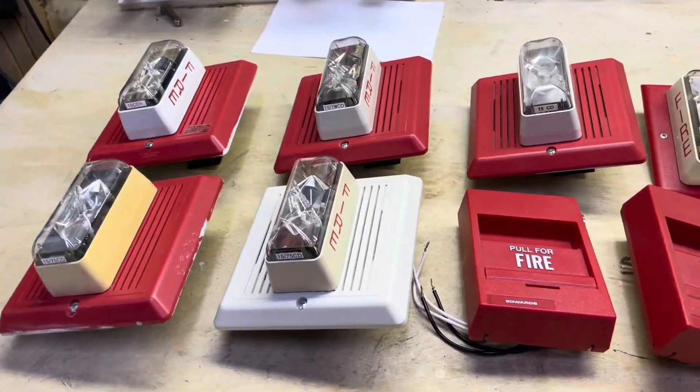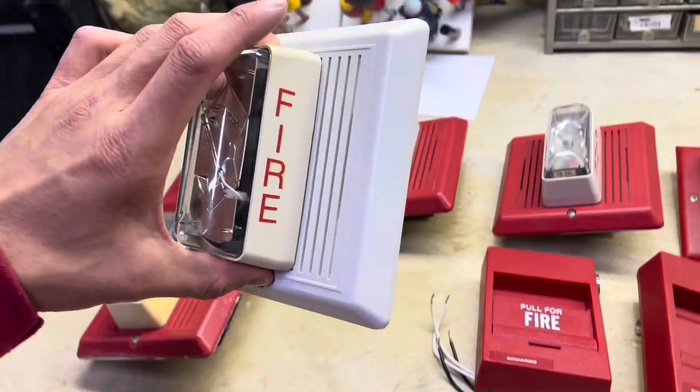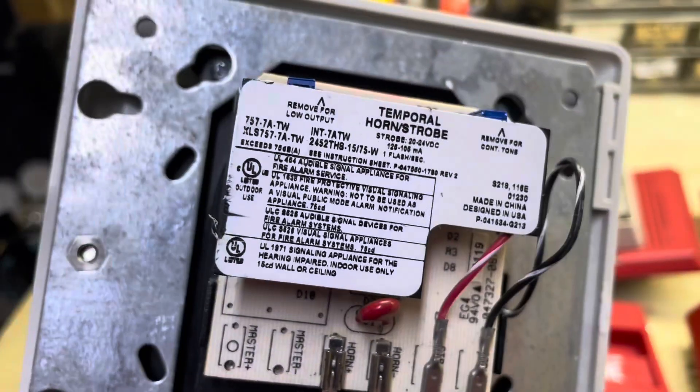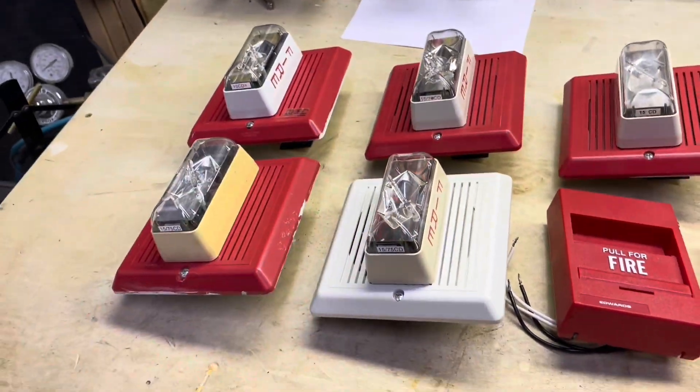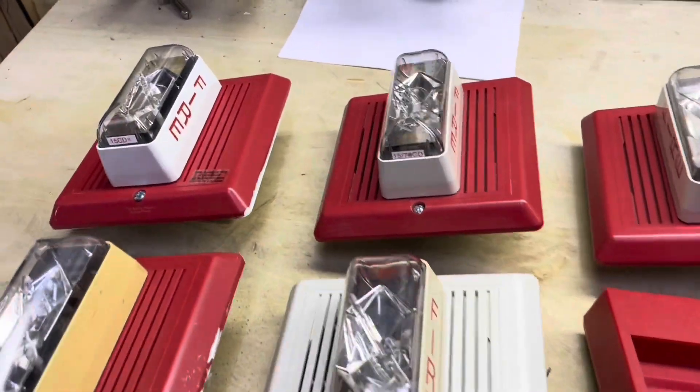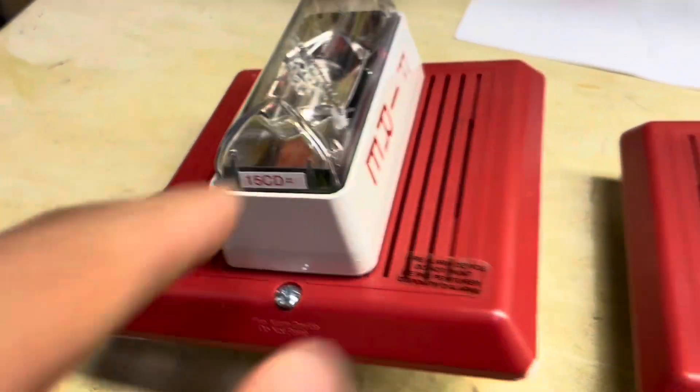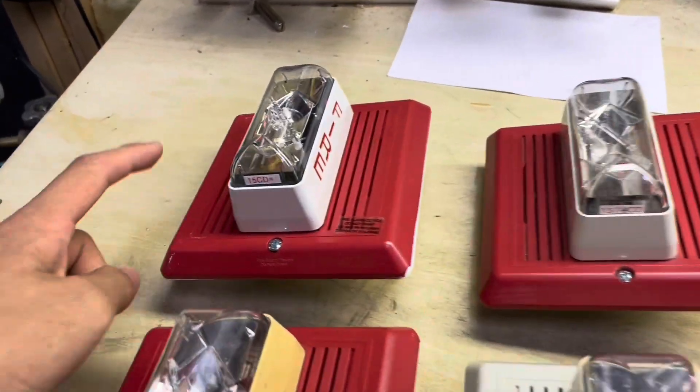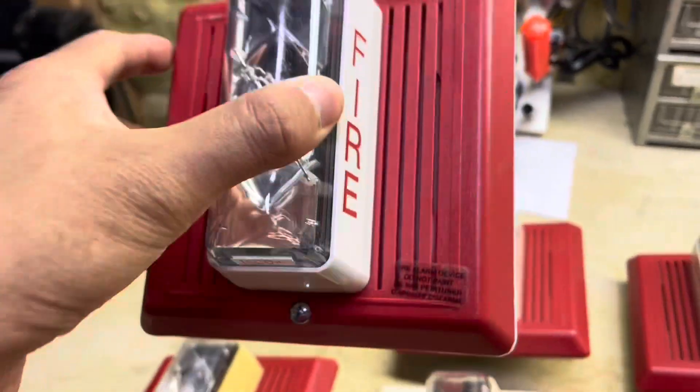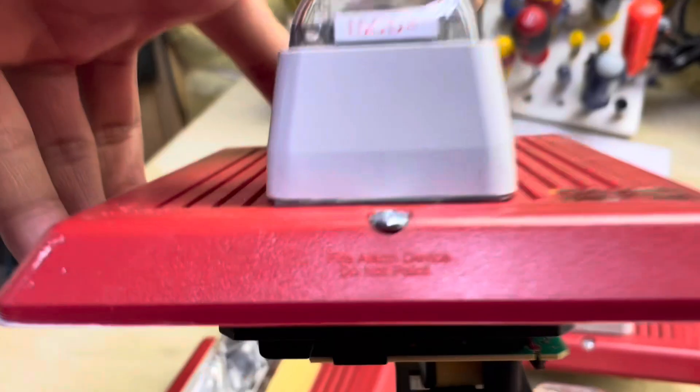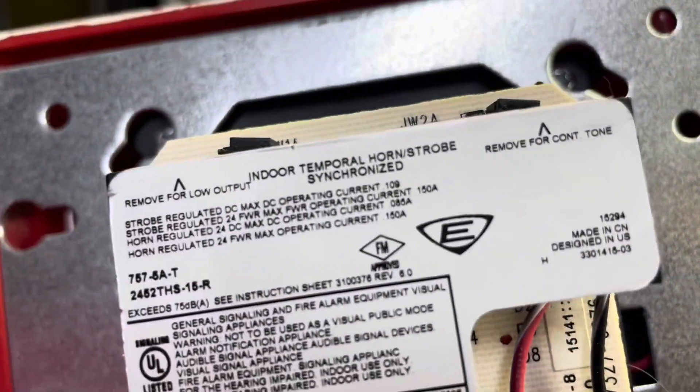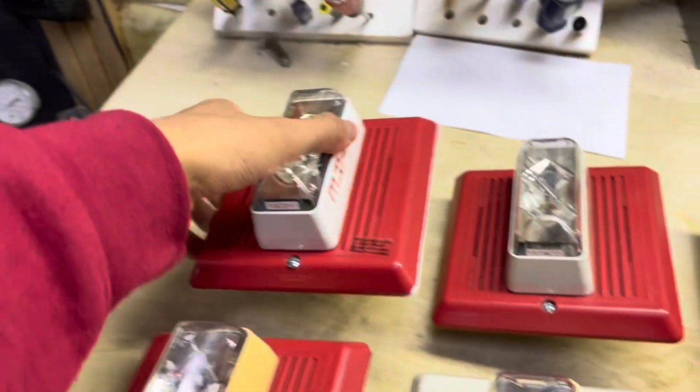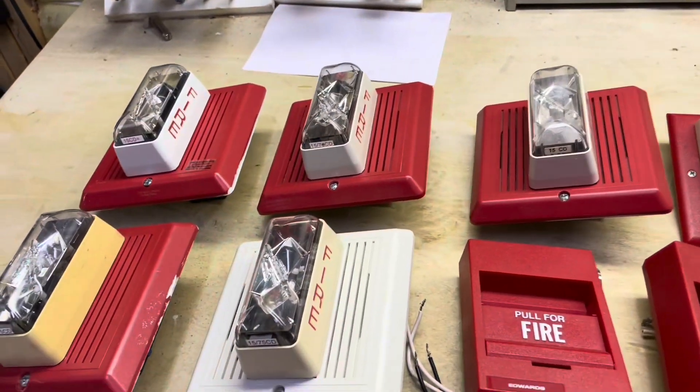These right here are the Edwards 757 Integrity Series of horn strobes. You can see here on the back, these are not going to synchronize with each other except for these two, because these older devices are non-syncable. But the ones with the red labels are considered enhanced, so these ones are pretty new, especially this one. Here's the modern Edwards logo. I think these are still being manufactured, but the rest of these are kind of old.